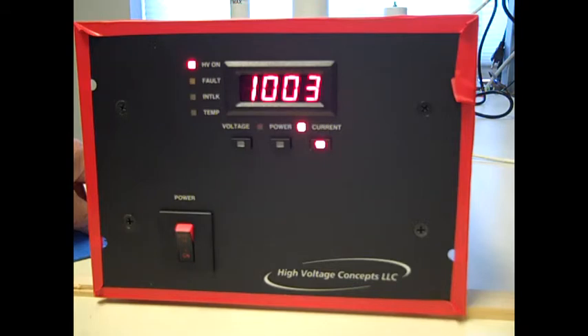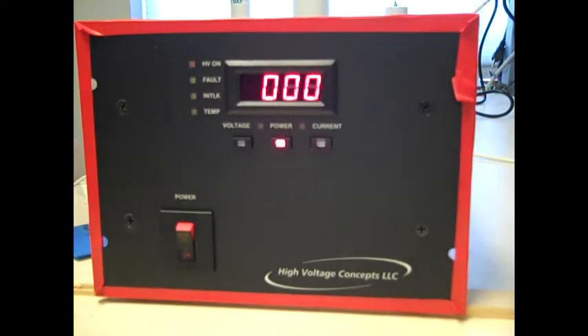Now we're going to put a dead short on the power supply and see what happens when we do that. Okay, so now we're back and we're looking at the power supply under the conditions of shorted output. Maybe the magnetron has failed, or it's shorted, or there's a high voltage cable that's shorted out that has failed, or some other connection inside the chamber has a problem. And we're going to turn on the high voltage and show you what happens to the power supply when we do this. So we're going to apply high voltage right now, and you see it comes up, tries to make an attempt, and then shuts down.